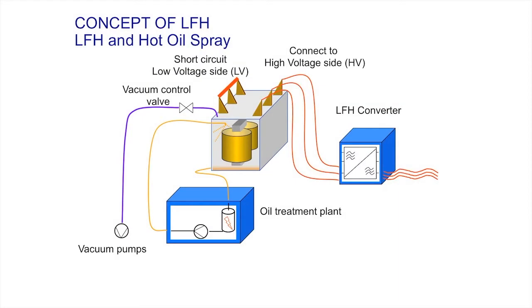Overview. General function. With this plant, 3-phase and single-phase transformers can be dried. The windings of the transformers are heated with low-frequency current. Other parts inside of the transformer are heated with oil circulation or hot oil spray.